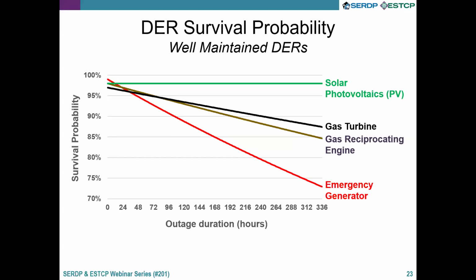People often don't see this themselves because rarely do they run their generators during testing for more than 30 to 60 minutes. But this is based on very large data sets, and it assumes the generators are well maintained. Most people in this field know that unfortunately many times generators are ignored and not well maintained. If maintenance procedures don't meet UFC code or industry standards, reliability drastically drops.